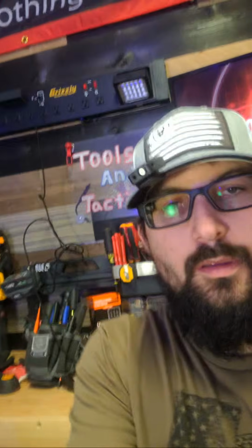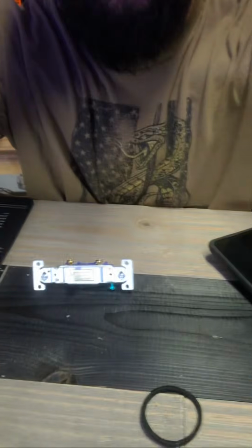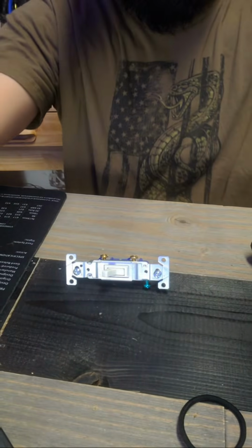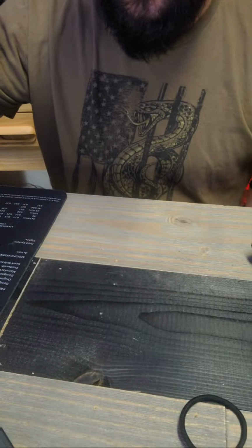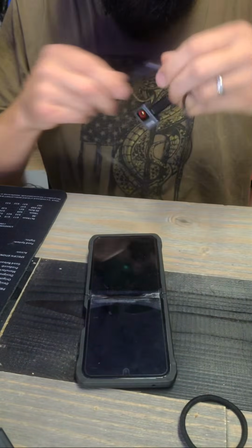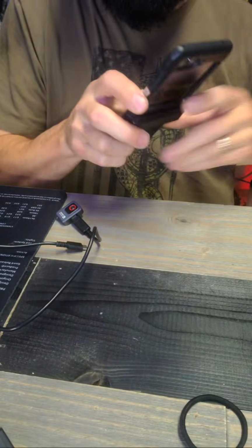What we're going to do is take a connection and purposely loosen it on an air conditioner so it's drawing a good load. We're going to show you how to find the problem real time and how to verify the problem. And like I said in the short, just because you found a loose connection on infrared doesn't always mean we have a problem. So we are going to show you how to hook this up.